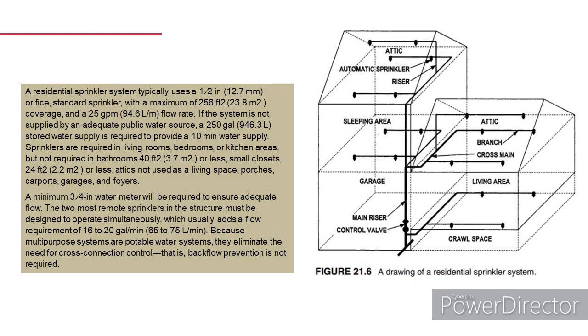Sprinklers are required in living rooms, bedrooms, or kitchen areas, but not required in bathrooms 40 square feet, 3.7 square meters, or less, small closets, 24 square feet, 2.2 square meters, or less, attics not used as a living space, porches, carports, garages, and foyers. A minimum 3/4 in water meter will be required to ensure adequate flow.